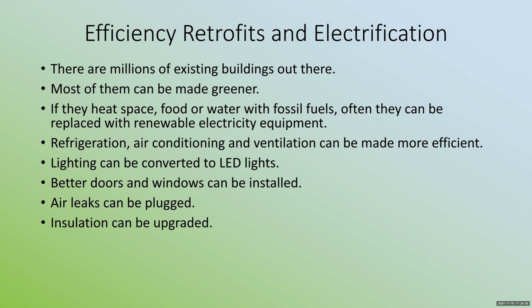Upgrade the insulation, but you can go too far on that. Every time you double your insulation thickness, you cut in half the amount of energy transfer through it, but you reach a point of no return. I've done the math here in Florida—anything over R19 is a waste of money, because the temperature difference across the attic isn't that large. The energy saved isn't worth it; better to put that money into a more efficient air conditioner or something else. That's the kind of exercise you need to do to make sure you do the right thing.